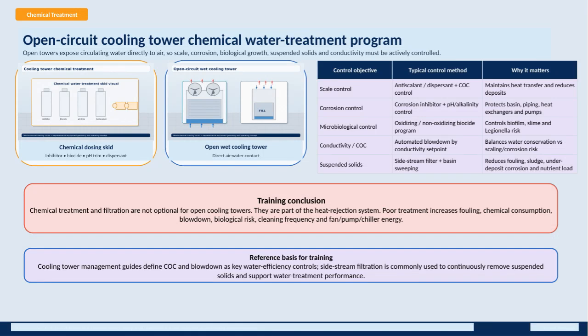Since these towers expose circulating water directly to the air, it's crucial to actively manage several factors, including scale, corrosion, biological growth, suspended solids, and conductivity. The primary goal here is to maintain optimal heat transfer efficiency and protect the cooling system components. To achieve this, we use a chemical dosing skid that delivers inhibitors, biocides, pH trim agents, and dispersants.